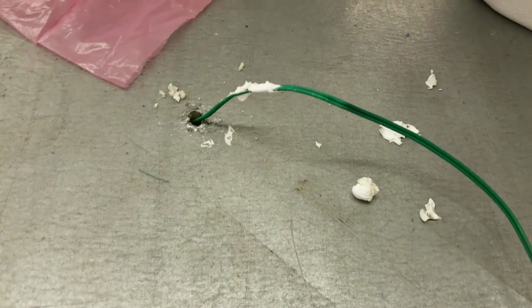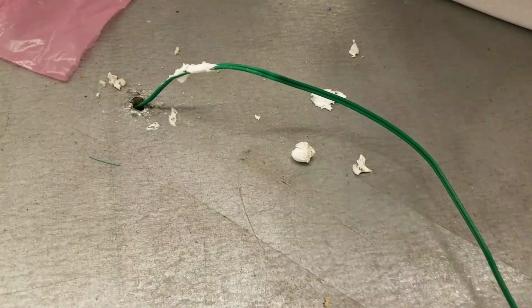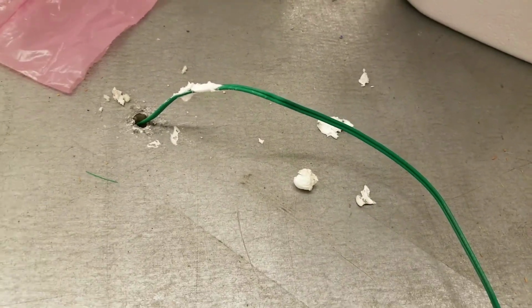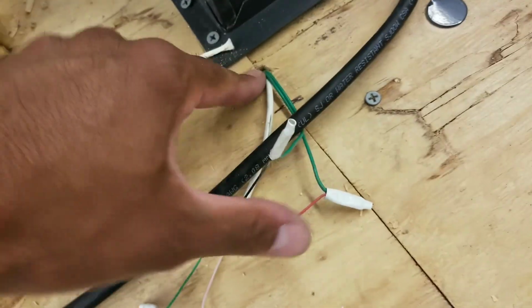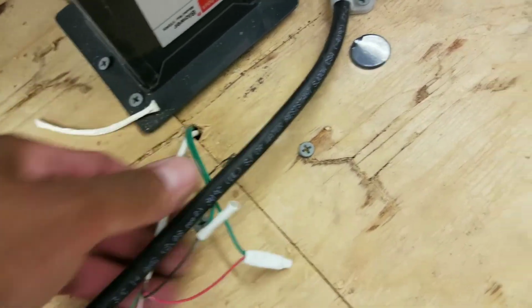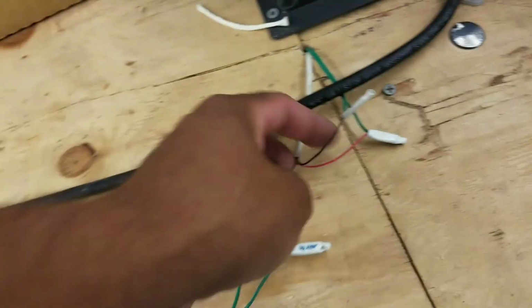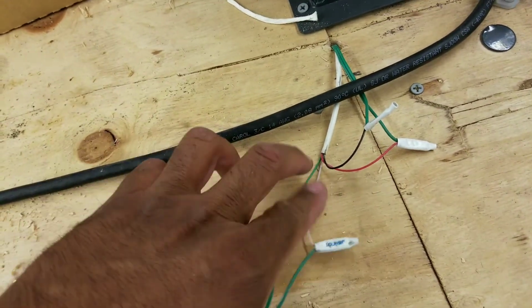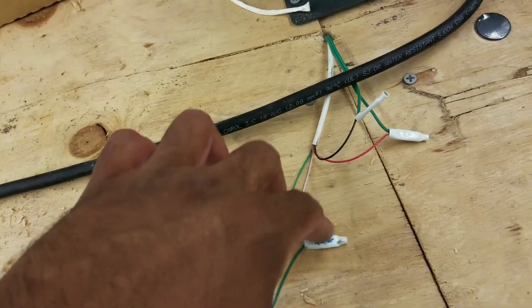Okay, there is the hole, pulled the old insulation out, which is, I don't know what they use, but that stuff is hard in there. So that's the old sensor. Trace it out. It went under here, so I took it out. Made a hole right here so it could come out because it was really trapped under here. It looked like it was pinching. And there's two types of sensors on here. This wire for this sensor, this is what I need.